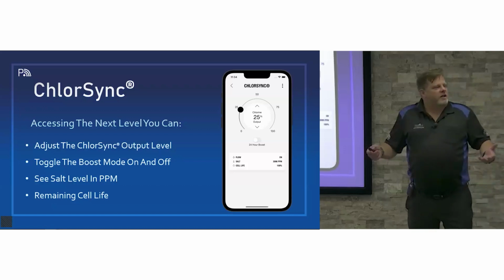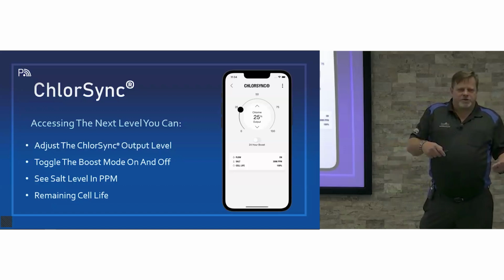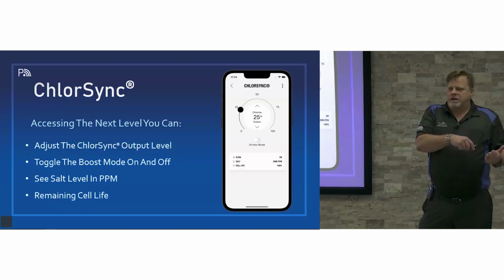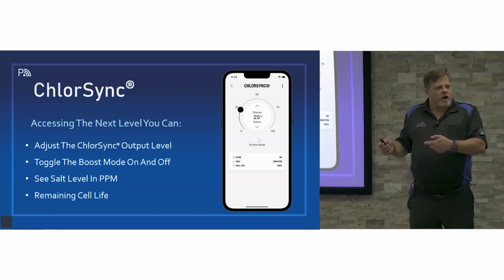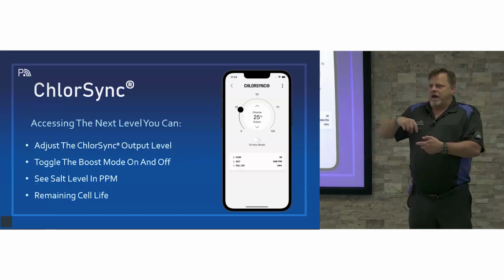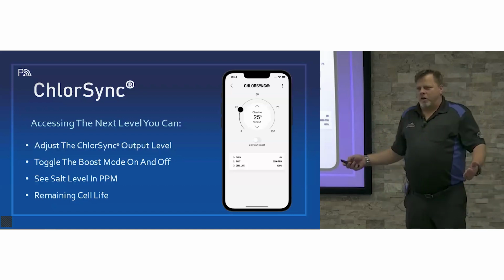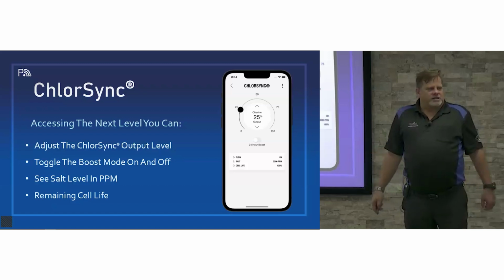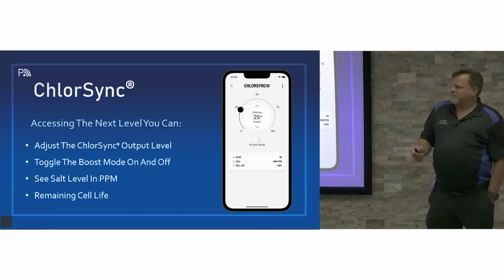And all of this is about safety, because let's face it, we're temperature compensated. So if it's running at 80%, maintaining a 15,000 gallon pool at 80 degrees, and you switch it to spa mode, now you're running a temperature up to 104. The system has temperature compensation, it'll jack that unit up to 100% output. Now you're not taking care of 15,000 gallons, you're on 350 gallons, and within 15 minutes that homeowner's sitting in a chlorine bath, bleaching their $300 bathing suit down to maybe 2 uses before it falls apart.